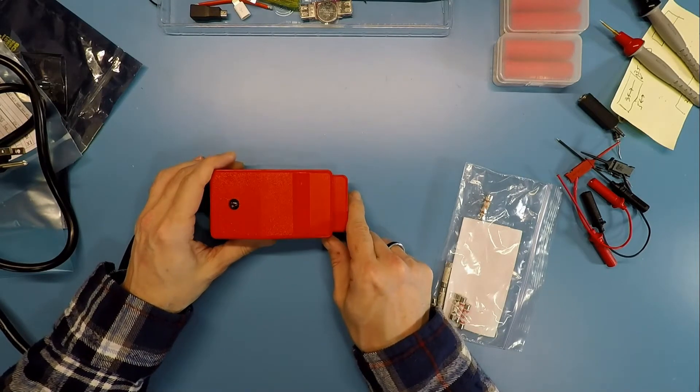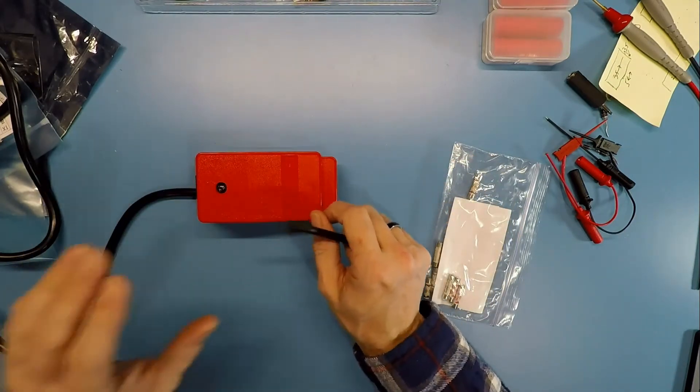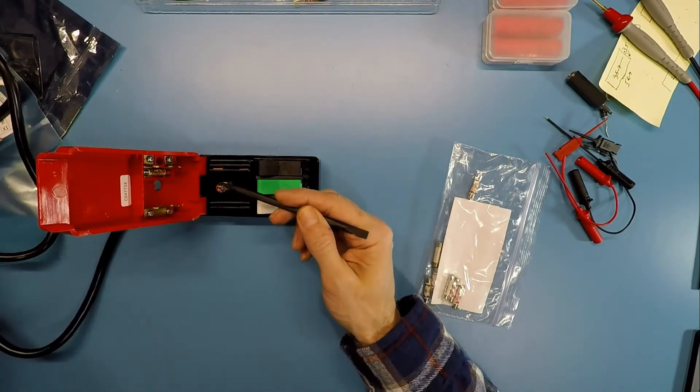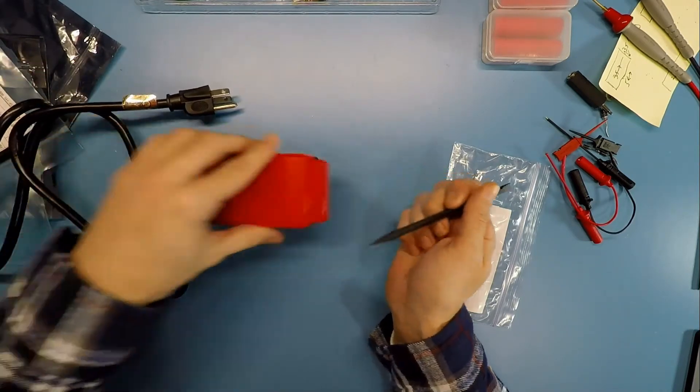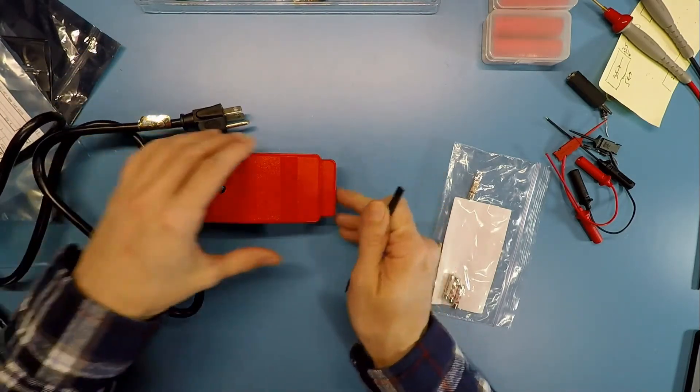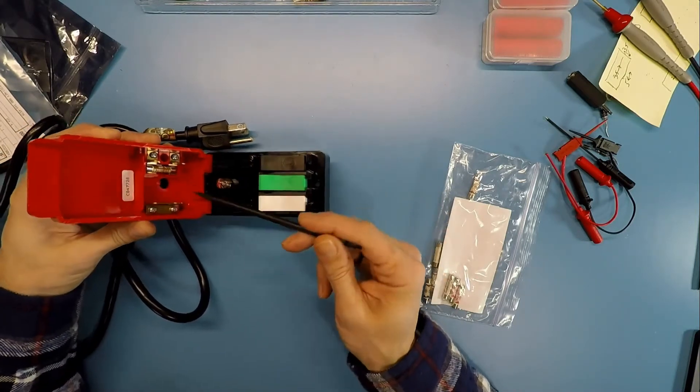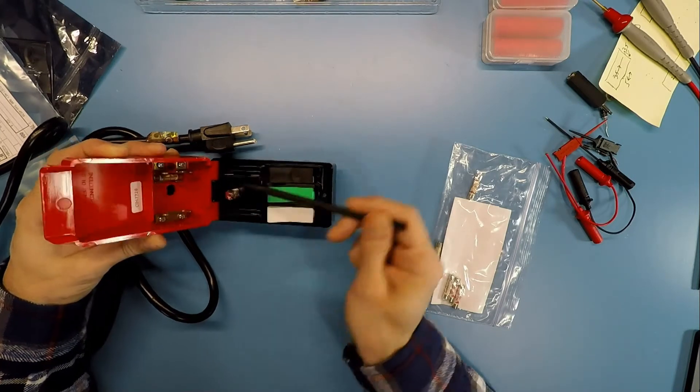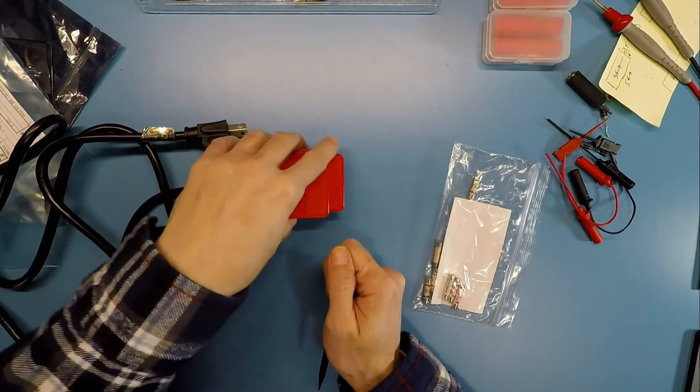Here's the actual quick test clip unit, looks pretty good. The neon lamp indicates that you have power plugged in, but does not indicate that these clips are live. If you have this plugged into the wall, the neon lamp tells you the circuit is possibly live. The circuit is not actually live until these pieces come down and make contact to complete the circuit.